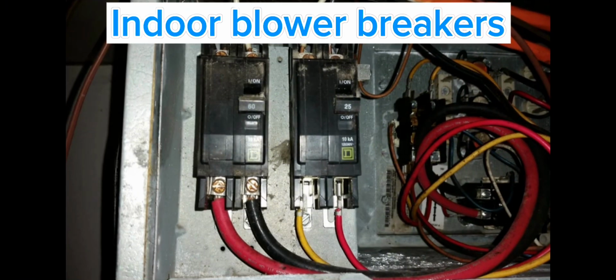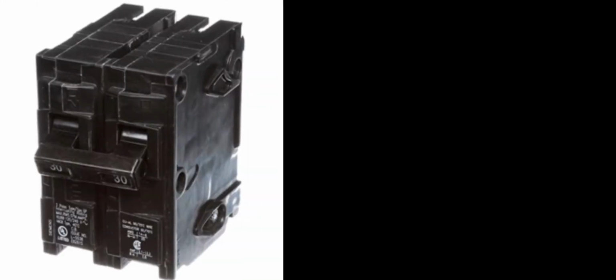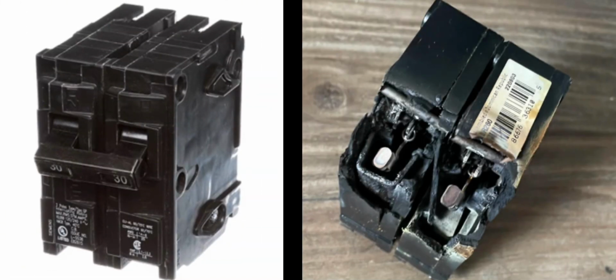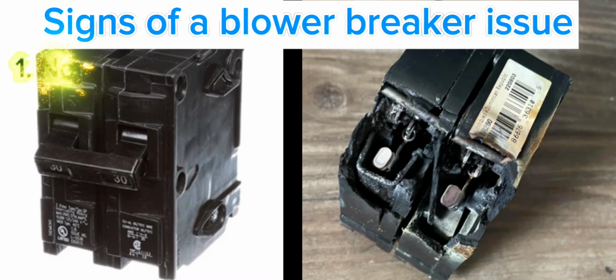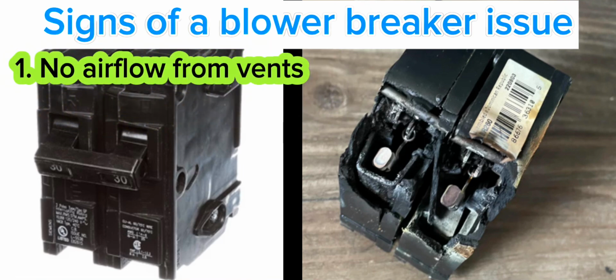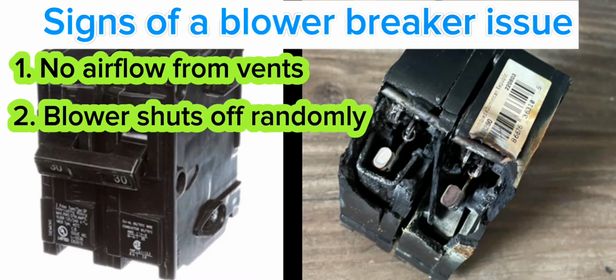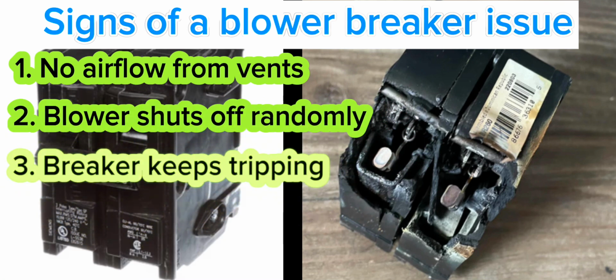Your indoor blower motor has its own breaker inside the air handler, separate from your main electrical panel. This breaker protects the motor from power surges and overloads. If your indoor blower motor suddenly stops working, check this breaker first. If it's tripping repeatedly, you could have a bigger problem, like a failing motor, a bad capacitor, or even an electrical short.